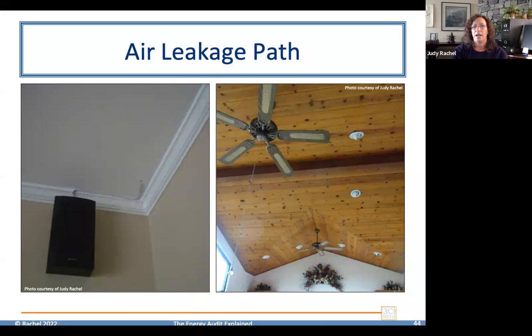They can be as small as this hole for the speaker system into the attic, and easily sealed if somebody realized that it's an air leakage pathway and that it matters. Or they can be as large as a tongue and groove ceiling like this, which is pretty much a complete air leakage pathway unless somebody paid attention to the proper details when it was first installed. The blower door will help you show whether that's the case.